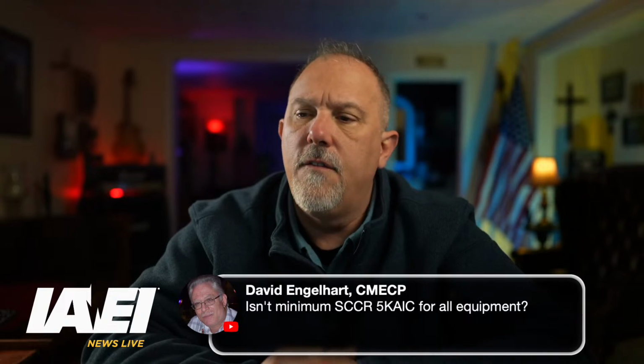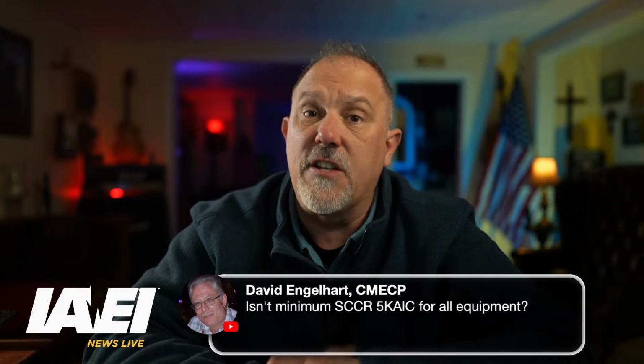We already talked about a minimum short circuit current rating, 5 kA for breakers and fuses. David, I would argue, yeah, I think you're okay. I think for a fuse, the minimum is 10K. For a breaker, it's 5K if it's not labeled. But as I said, if I go to, let me do this real quick. I'm going to call up the UL standard for 508. UL 508A, I'm just going to grab this and go Control F. It's not there.